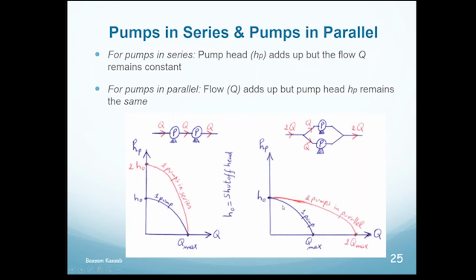But sometimes you need more flow, not more head. If the projected demand in the system in the future is going to be larger, so you need more flow to come out, you can add another same size pump or another small pump. It's up to you. But the diagram here is for another same size pump. If you have one pump, that's the pump curve. But if you have 2 pumps in parallel, you are going to have double the flow with the same head, because the head differential between this node and that node is still the same for the pump. One pump or two pumps, it's the same head differential, but you double the flow.